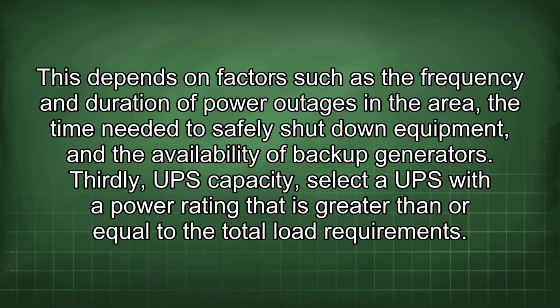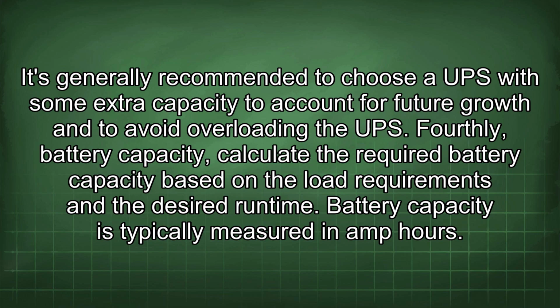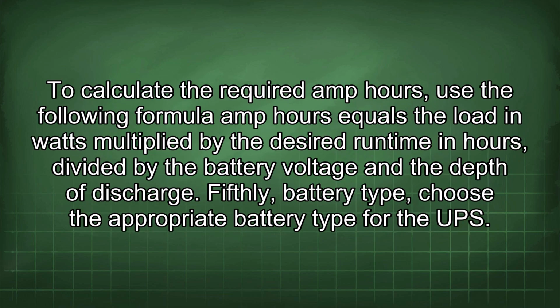Thirdly, UPS capacity. Select a UPS with a power rating that is greater than or equal to the total load requirements. It's generally recommended to choose a UPS with some extra capacity to account for future growth and to avoid overloading the UPS. Fourthly, battery capacity. Calculate the required battery capacity based on the load requirements and the desired runtime. Battery capacity is typically measured in amp hours. To calculate the required amp hours, use the following formula: amp hours equals the load in watts multiplied by the desired runtime in hours, divided by the battery voltage and the depth of discharge.